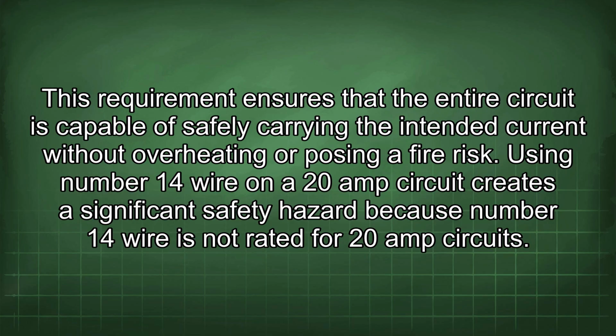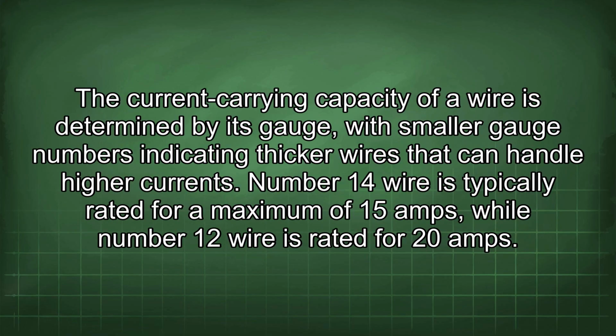This requirement ensures that the entire circuit is capable of safely carrying the intended current without overheating or posing a fire risk. Using number 14 wire on a 20 amp circuit creates a significant safety hazard because number 14 wire is not rated for 20 amp circuits. The current carrying capacity of a wire is determined by its gauge, with smaller gauge numbers indicating thicker wires that can handle higher currents. Number 14 wire is typically rated for a maximum of 15 amps, while number 12 wire is rated for 20 amps.